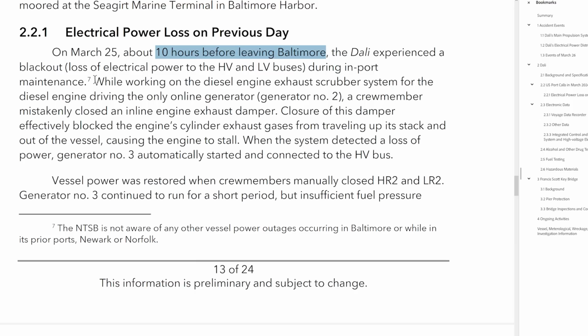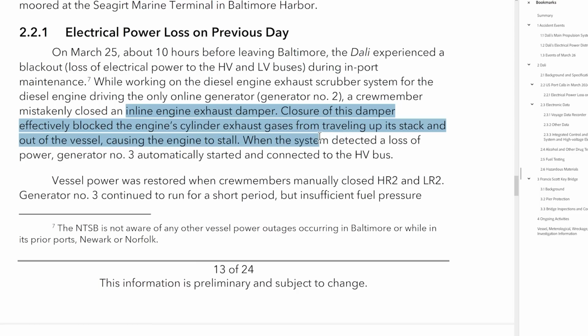It says what happened here: a worker was working on the diesel engine exhaust scrubber for the diesel engine driving the only online generator, generator number 2. A crew member mistakenly closed an inline exhaust damper. Closing this damper blocked the engine's cylinder exhaust gases from traveling up its stack out of the vessel, and it caused the engine to stall.